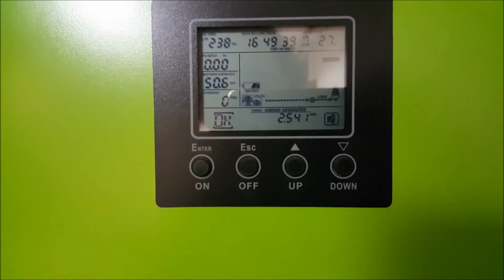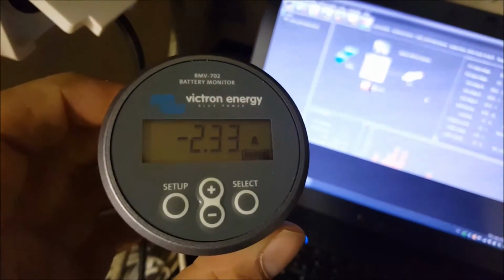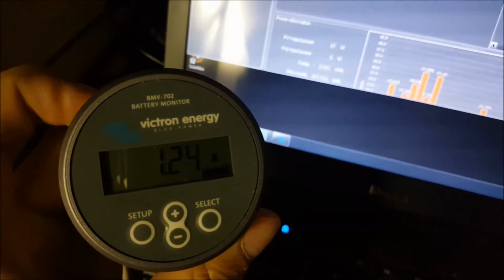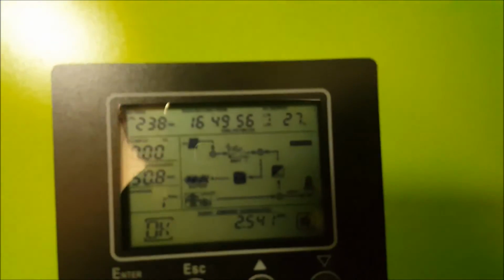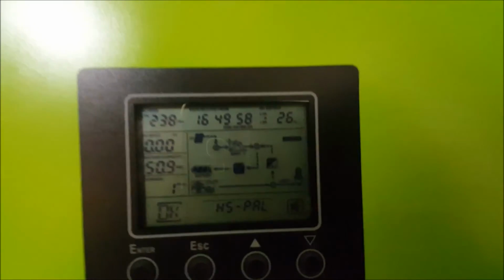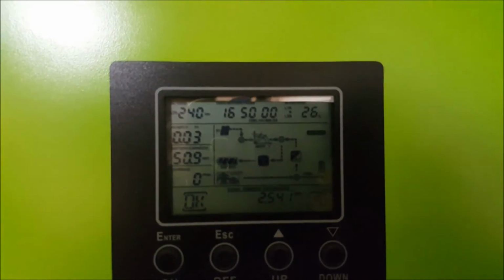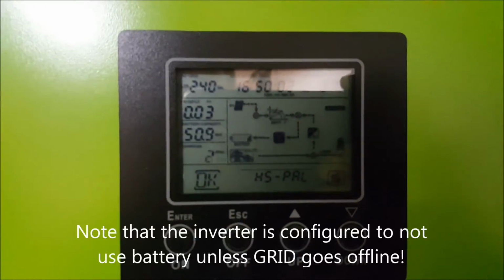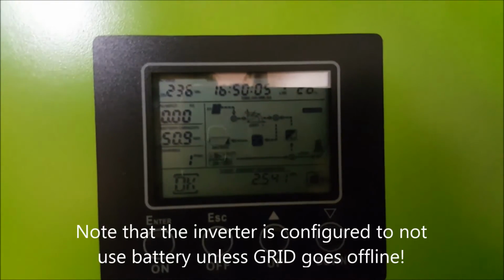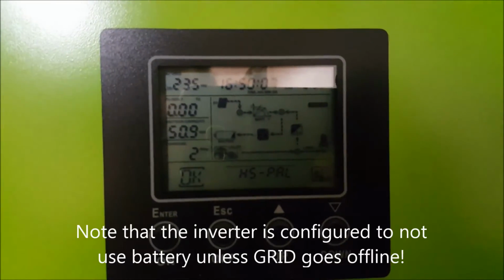So why is it using the battery when it shouldn't? If I hook up one of the PV arrays again, you will see that it immediately stops using the battery and actually starts pumping in battery. That's because the AC is charging a little bit. Is the internal metering wrong in this unit? Because to me it looks like it doesn't meter the amperage going to the battery properly.